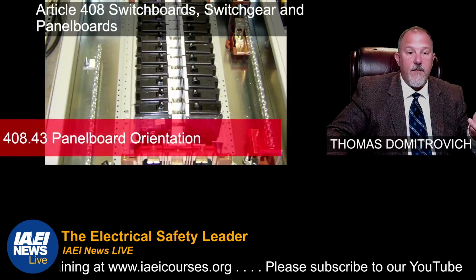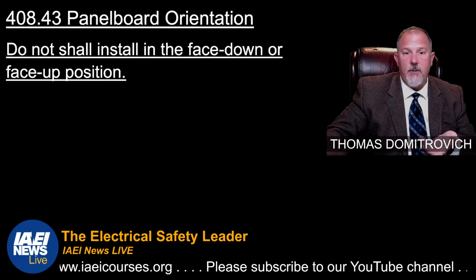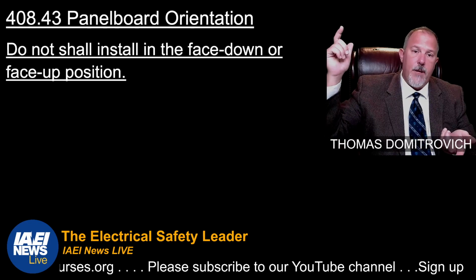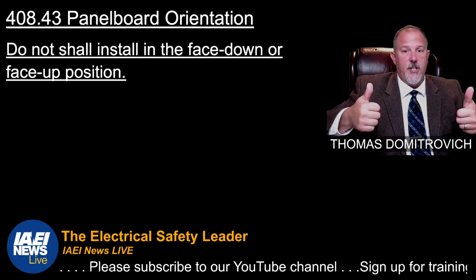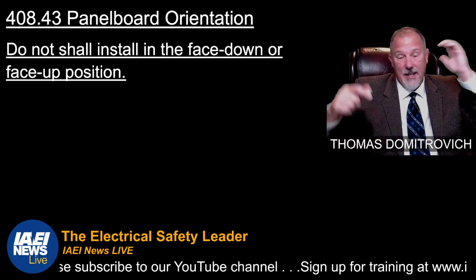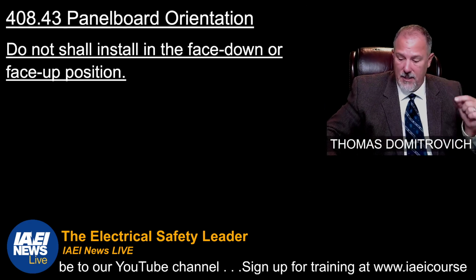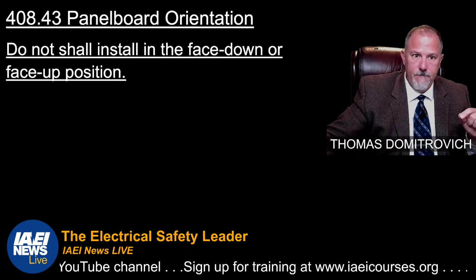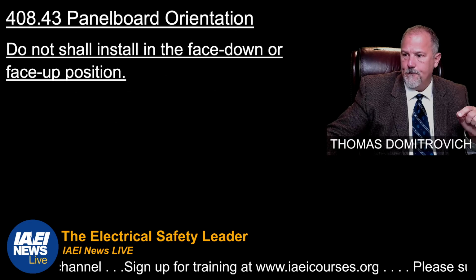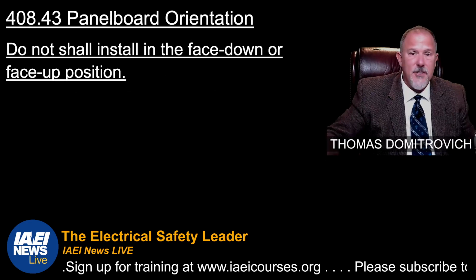All right, 408.43. This saw a little bit of a change. You can't put the panel board in the face up position. 2023 is going to tell you you can't put it in the face down position either. That's 408.43. And there's no exceptions.